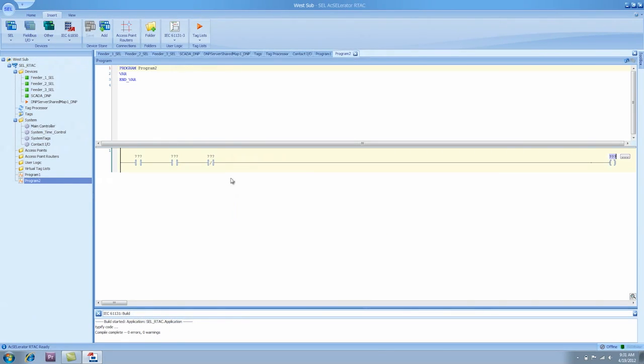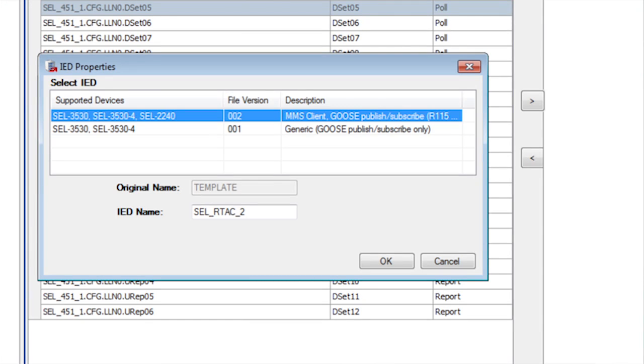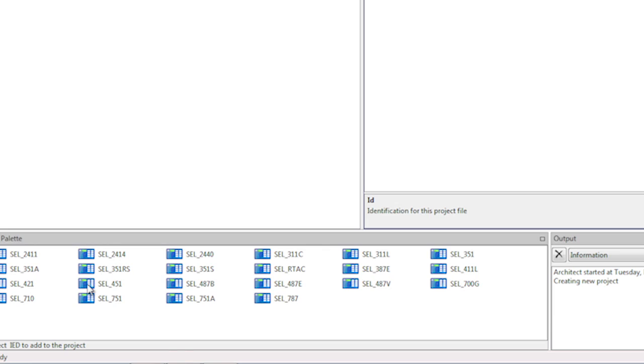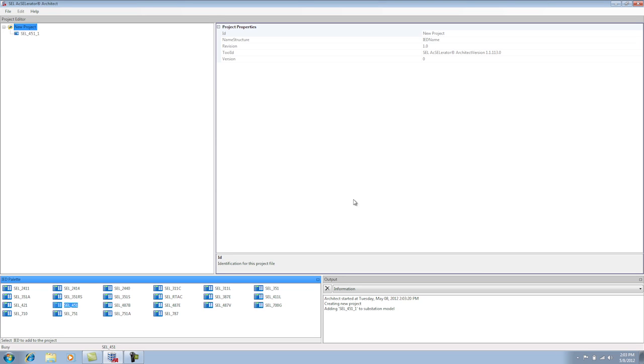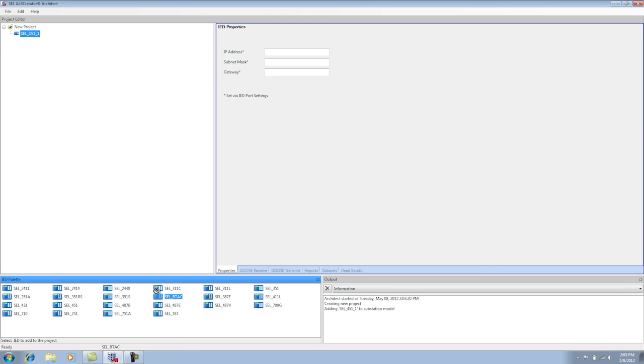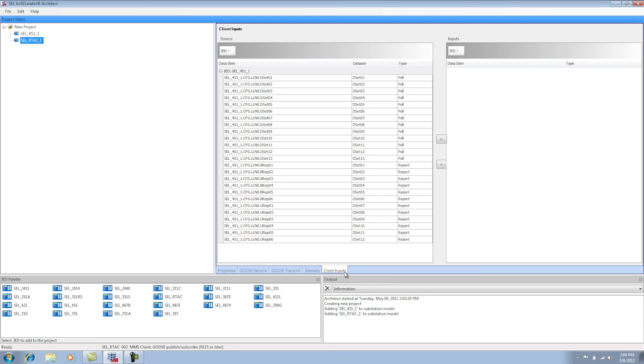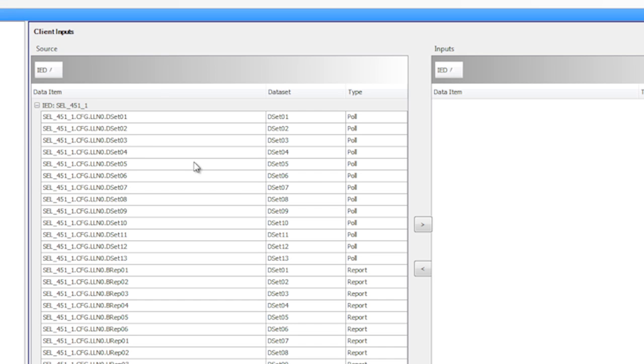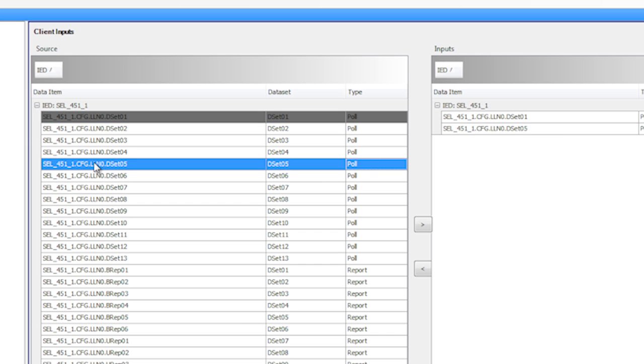The IEC 61850 MMS protocol is actually fairly complex, but we've used software to make the configuration extremely simple for the customer. Using Accelerator Architect, the customer can configure an SEL device or a non-SEL device simply by dragging the device configuration to a project pane. From that project pane, they can create an RTAC in there as well, and then select another tab and just map over the data that they want. That creates a file that they can then import into the RTAC, and the configuration is basically done.